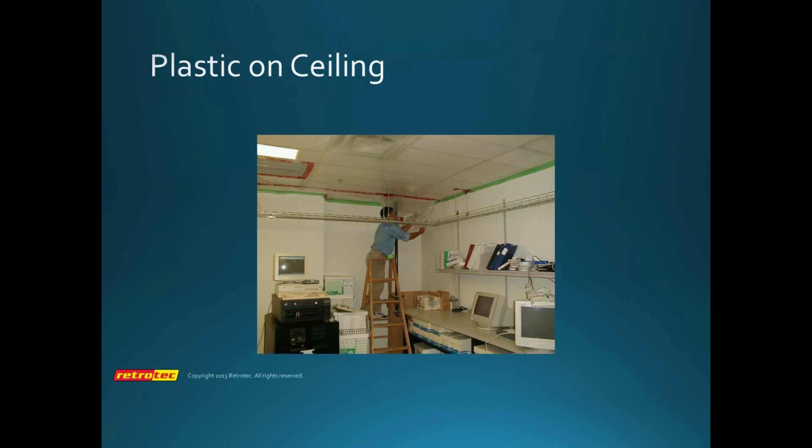One is to cover the ceiling in plastic, and I've done that I think 3 times in my life, and it takes anywhere from 2 to 6 hours depending on the size of the room to do a good job of that. That enables us to measure the size of the hole in the bottom part of the enclosure, which is where the agent leaks out.